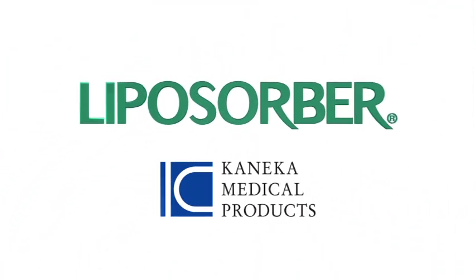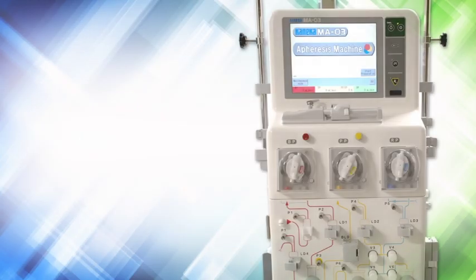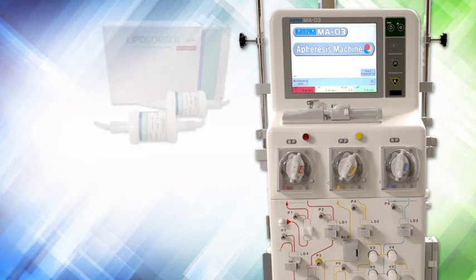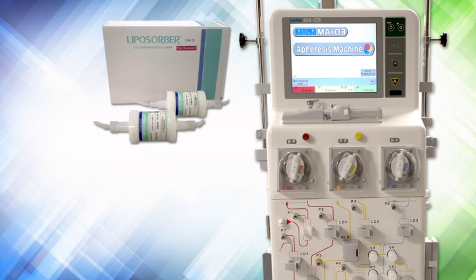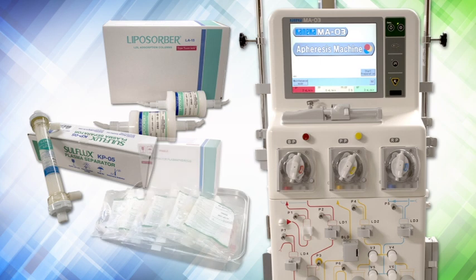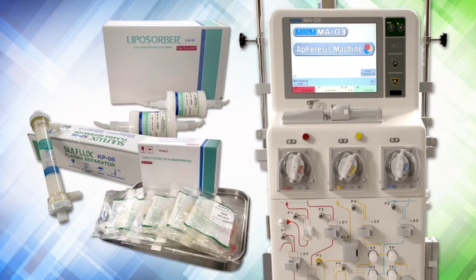The Liposorber LA-15 system is an integrated automated extracorporeal blood processing system comprised of the apheresis machine Kaneka MA-03, which controls and monitors the LDL apheresis procedure, and three single-use disposables: the Liposorber LA-15 LDL adsorption column set, which are two columns each containing 150 mL of dextran sulfate cellulose adsorbent, the Sulflux KP-05 plasma separator which contains polyethylene hollow fibers, and the tubing system for plasma apheresis NKM3R.